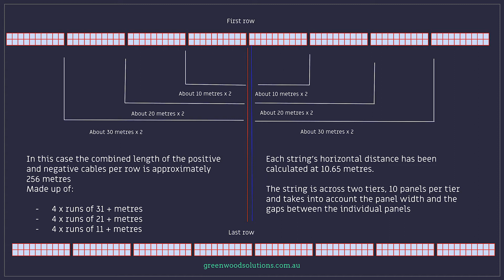In this case the combined length of the positive and negative cables per row is approximately 256 meters made up of four runs of 31 plus meters, four runs of 21 plus meters and four runs of 11 plus meters.